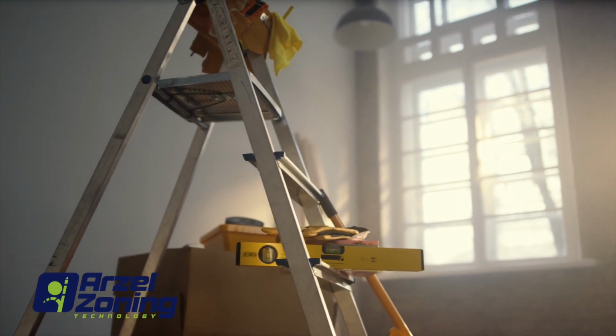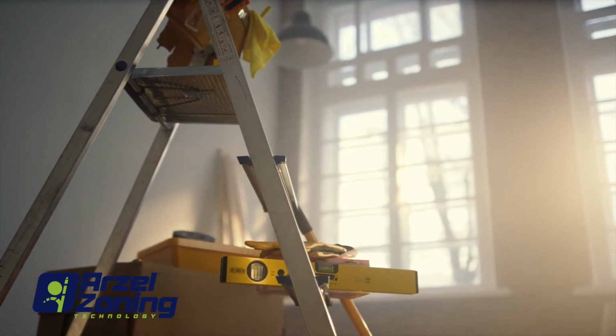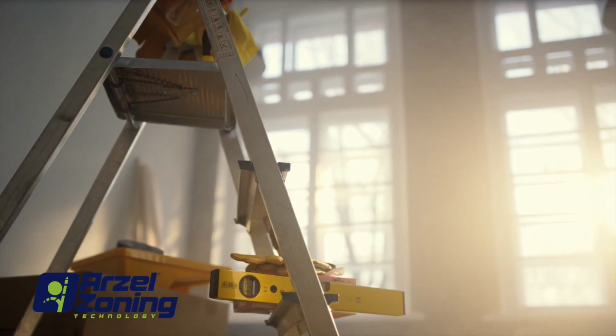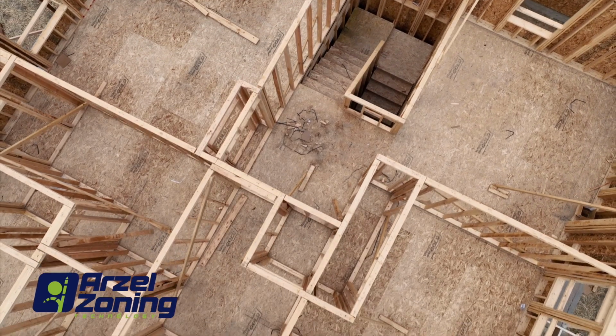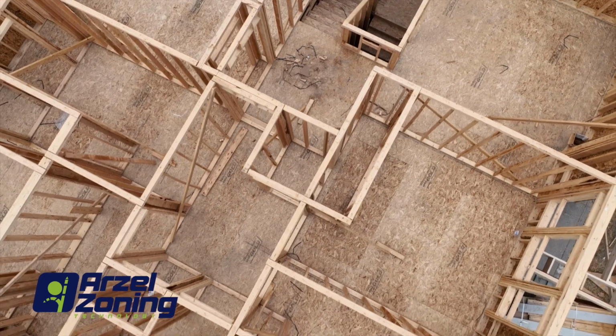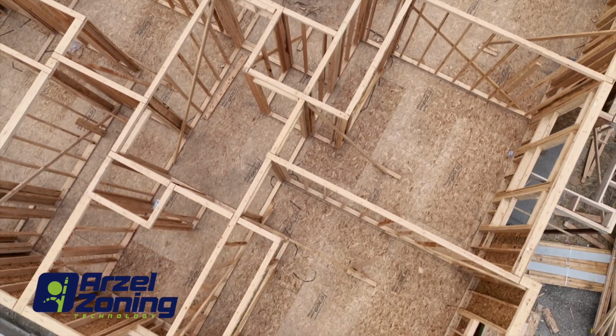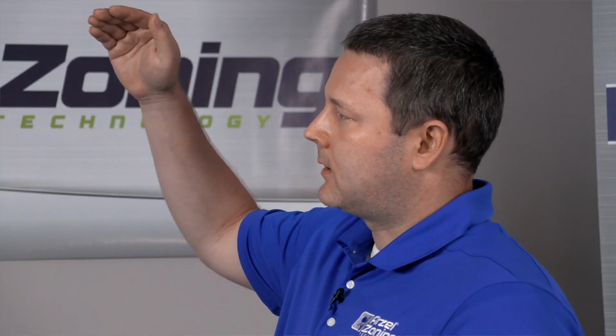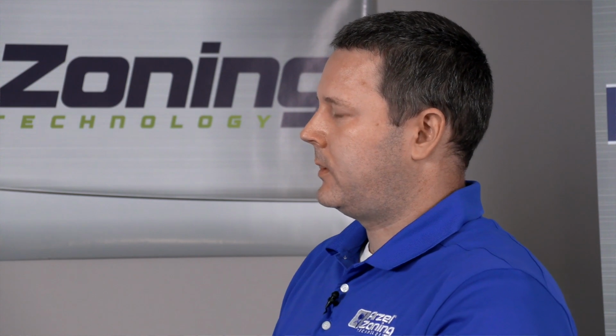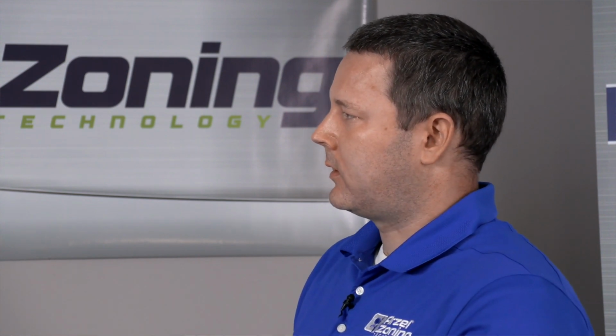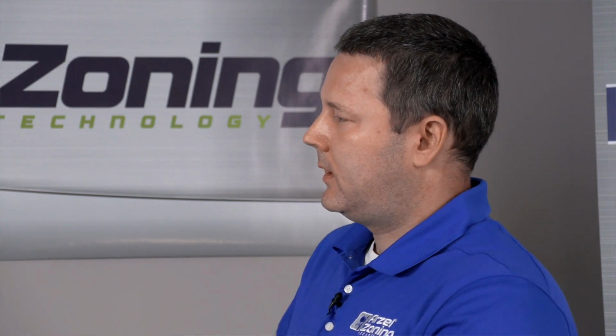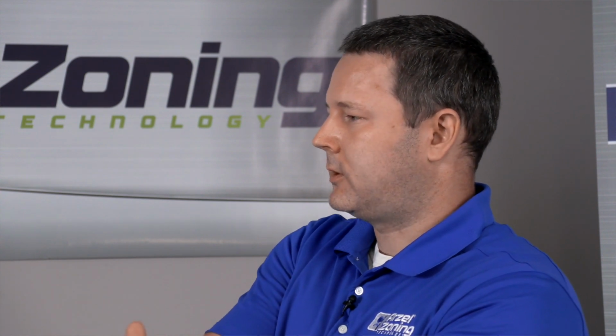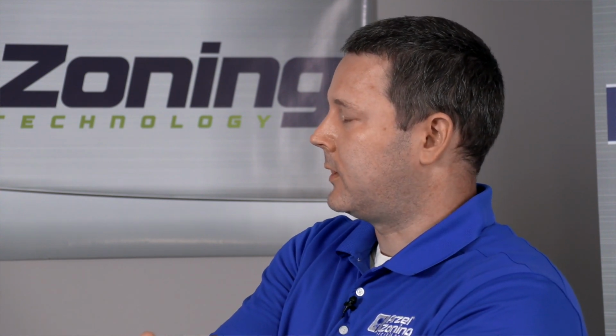Because maybe you've added a new room onto the back of the house, you've added a new suite, you've got family moving in and wanted to provide space for them, but you have a two-story house. That upstairs is probably going to need conditioning, and the new room is probably going to need conditioning, but the main part of the house probably won't. So by adding zoning, we can direct air from the main part of the house where it's comfortable, and send that to the addition without having to do any major duct modifications or upsize the equipment.